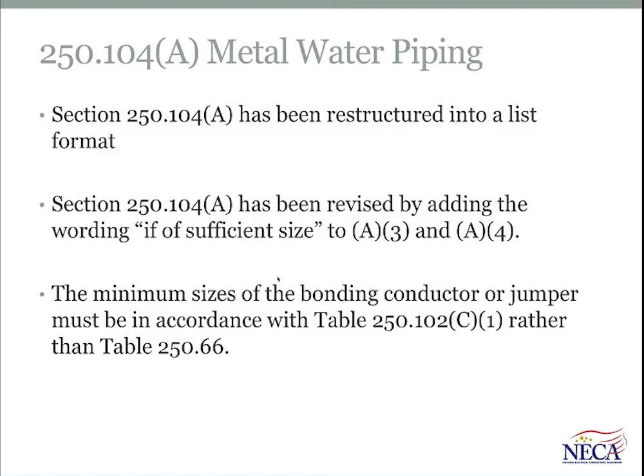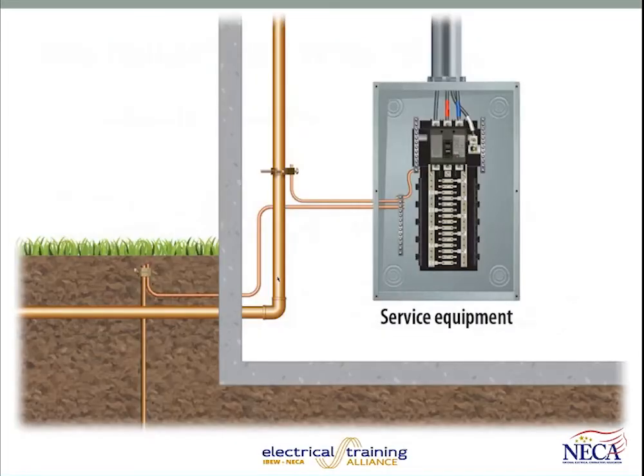So rather than use the maximum values in Table 250-66, the NEC now requires Table 250-102C1 to be used, which means that if you're dealing with a larger service or a larger separately derived system and you have to install a water pipe bonding conductor or structural metal framing member bonding conductor, you don't stop at 3/0 copper or 250 aluminum anymore. In the larger sizes, you have to apply the 12.5% rule. That's a significant change. So we're talking about a bonding conductor for piping systems that would be installed.